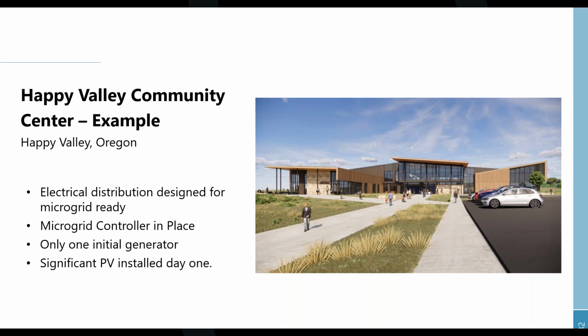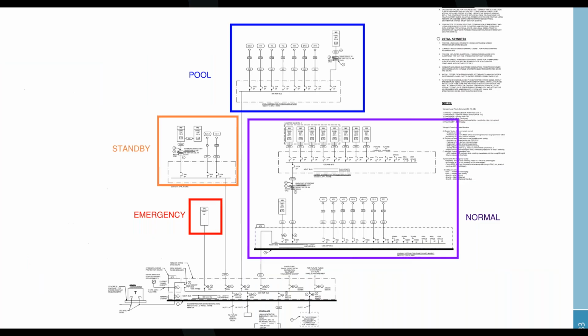This next slide shows how it's organized. At the bottom is your microgrid ready switchboard, and instead of transfer switch schemes, it's all done in the microgrid with the breakers switching, with a load priority applied to each. In this case we have emergency, standby feeding freeze protection and IT systems, then the pool, which is basically the first thing that will shed if required, and then normal is the rest of the building. All of this comes directly into the main switchboard and gets managed by the microgrid.